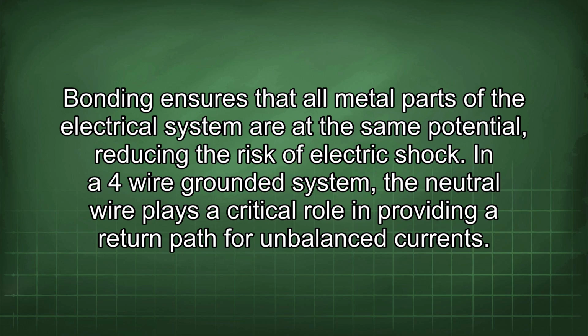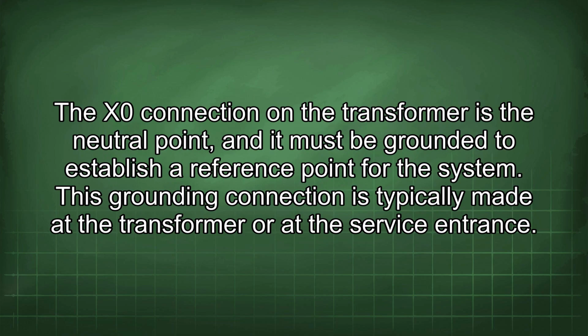In a 4-wire grounded system, the neutral wire plays a critical role in providing a return path for unbalanced currents. The X0 connection on the transformer is the neutral point, and it must be grounded to establish a reference point for the system. This grounding connection is typically made at the transformer or at the service entrance.